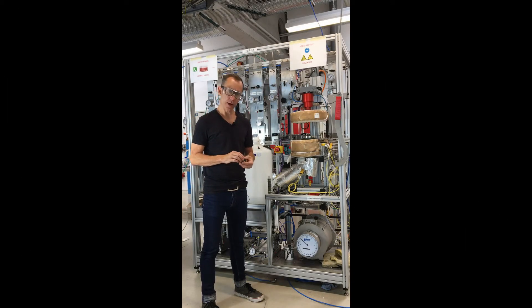Today I'll be introducing you to the latest BERTY-type reactor that ILS is going to be delivering. BERTY reactors are internal recycle reactors used for doing kinetic testing of heterogeneous catalysts at integral conversion levels — so where you have high conversion levels.